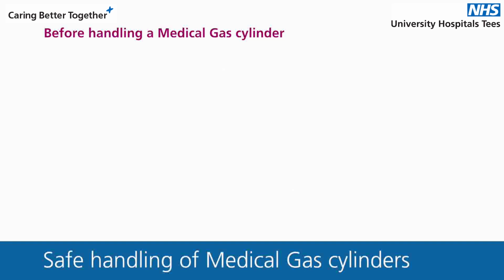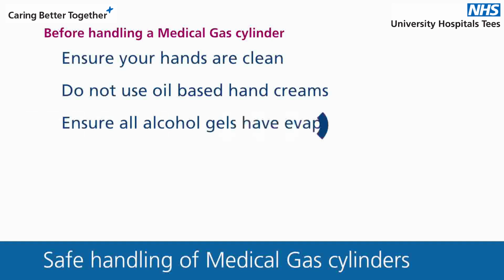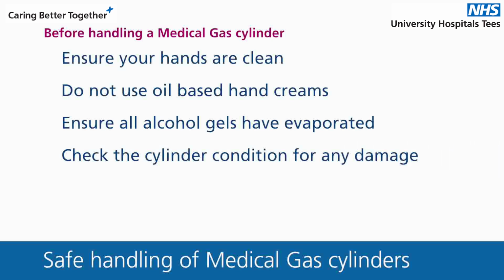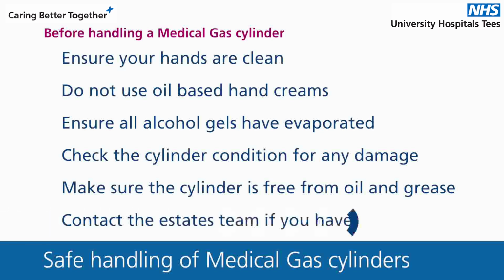Before handling a medical gas cylinder, ensure your hands are clean. Do not use oil-based hand creams and ensure alcohol gels have evaporated so your hands are completely dry when handling a cylinder. You must check the cylinder conditions to ensure there is no sign of any damage. The cylinder is free from oil or grease. You must contact the estates team if you have any concerns.